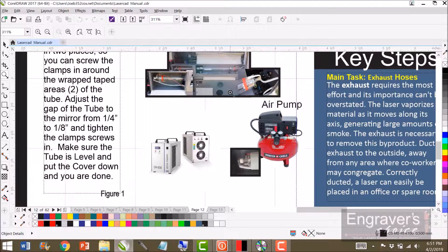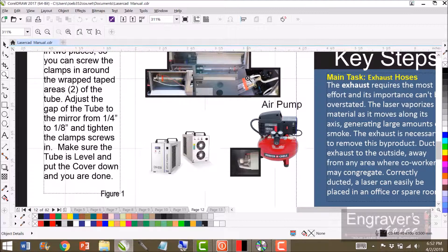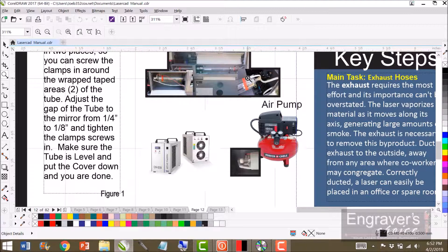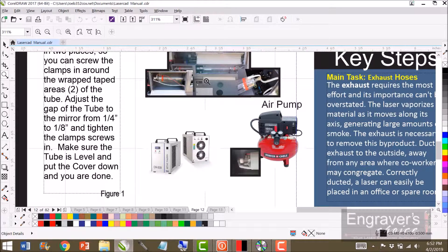Then you're going to inspect the tube to make sure there's no cracks on the tube and that all your wiring is hooked up. You may have to take four screws off the side. I usually take three of them, then the little door will slide down, and I put one back in to counter-torque each other. I leave it in thumb tight.